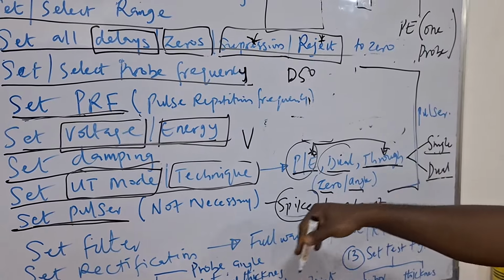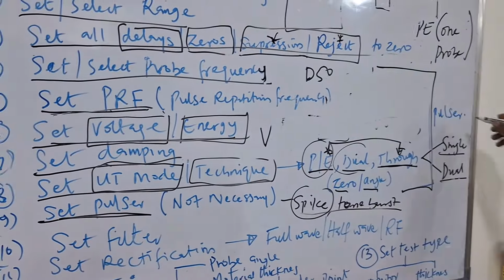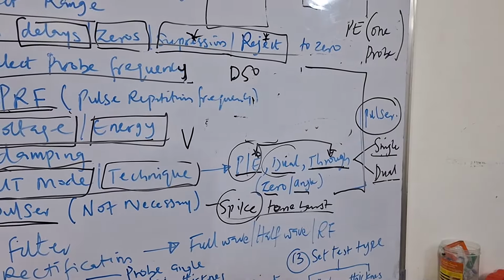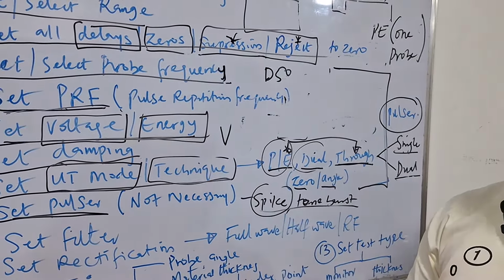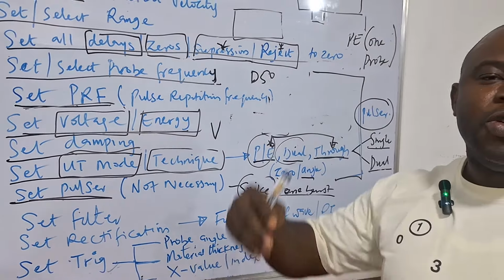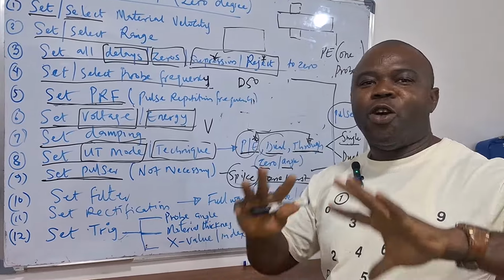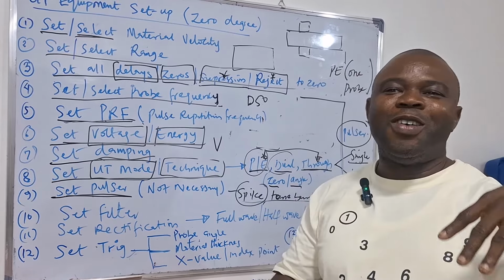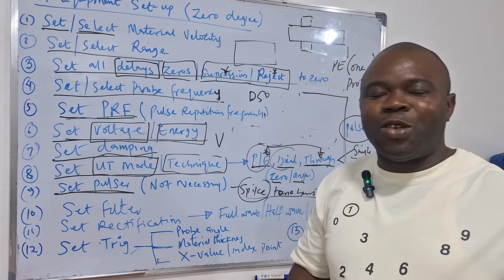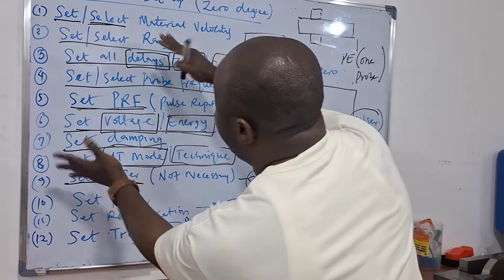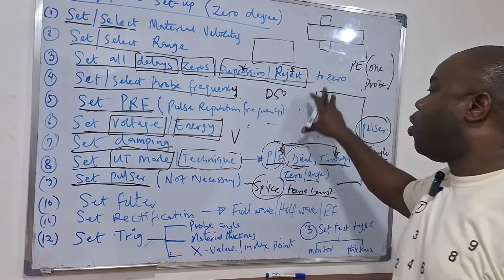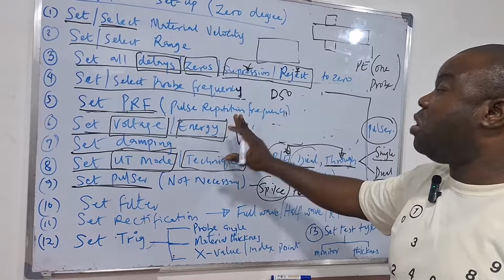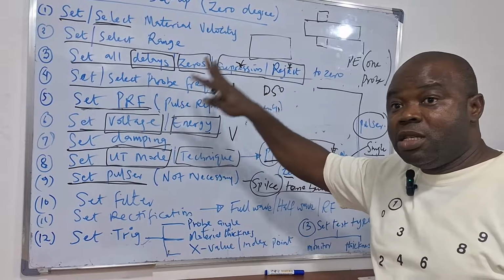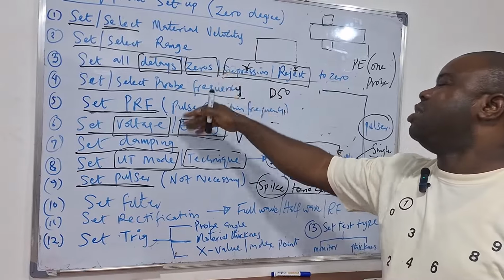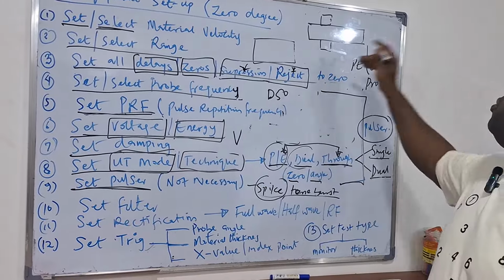From number 4 to number 9, they usually fall under what we call the pulser. If you get a UT unit, in principle you have your pulser setup and your receiver setup. In your pulser setup you have your pulse generator, your synchronizer or timer, and the rest, and they all work with this information. Some machines put it under pulser, others scatter it across the buttons, but whatever you're doing here is affecting the pulser. What do we mean by pulser? Whatever is being generated by the probe to the material.